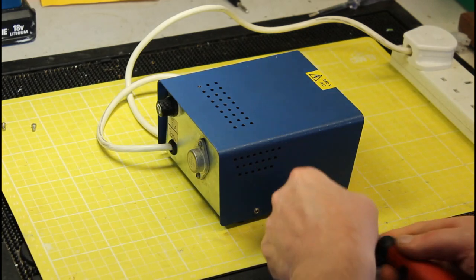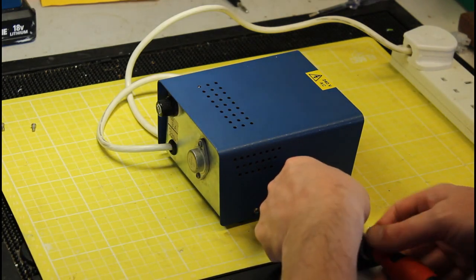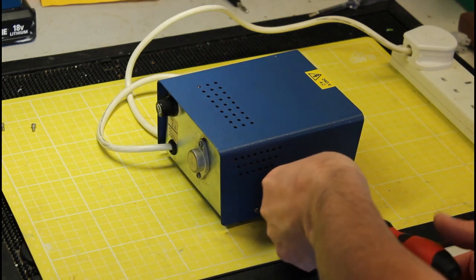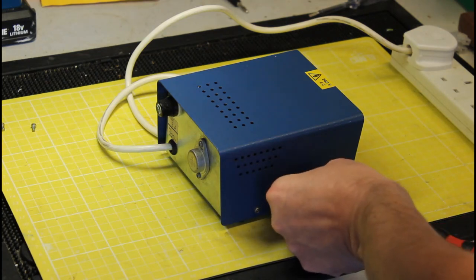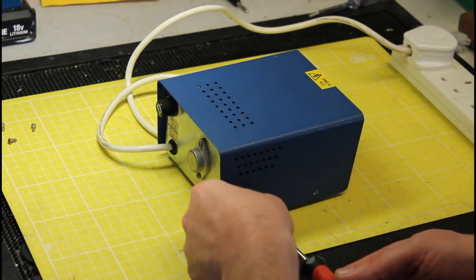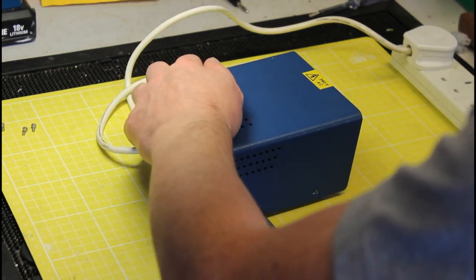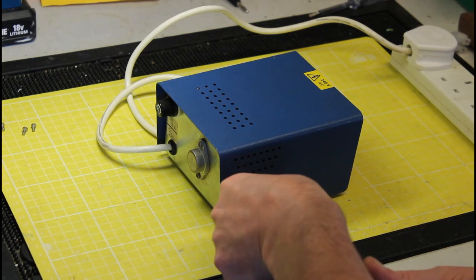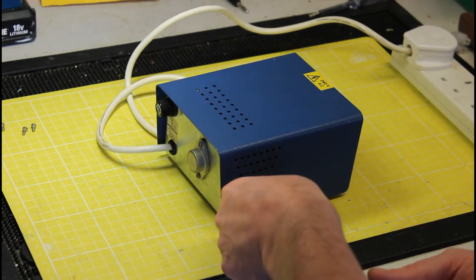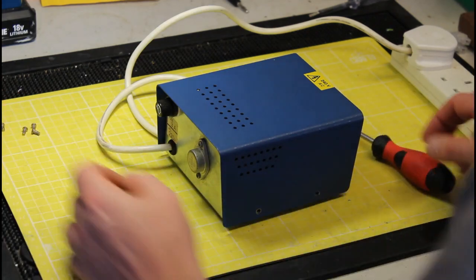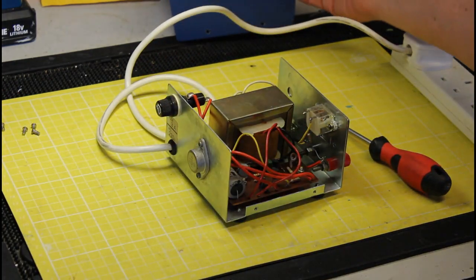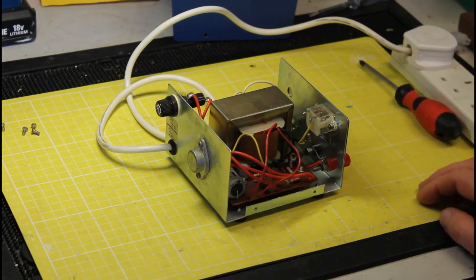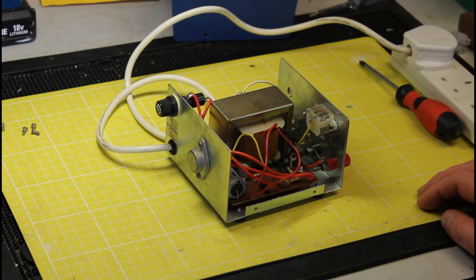Now we in the UK are nominally 230 volts, except we're not in this particular building - we're at 244 volts because we're fed by an 11,000 volt overhead power cable with a transformer on a pole. We're the only building on our own substation for half a mile, so it's a little bit higher here. What do you think the problem is? Well, the problem is if the output of the transformer is say 28 volts and we are 10% over, then that comes up to 30.8 volts.